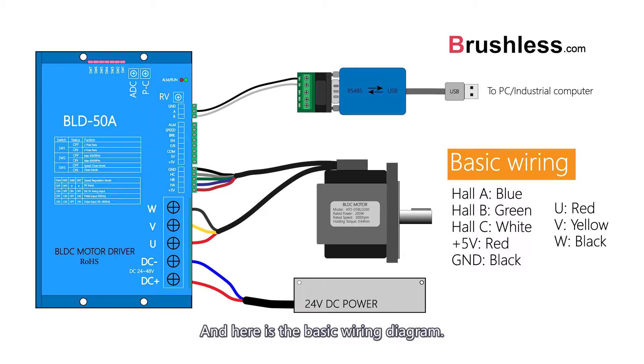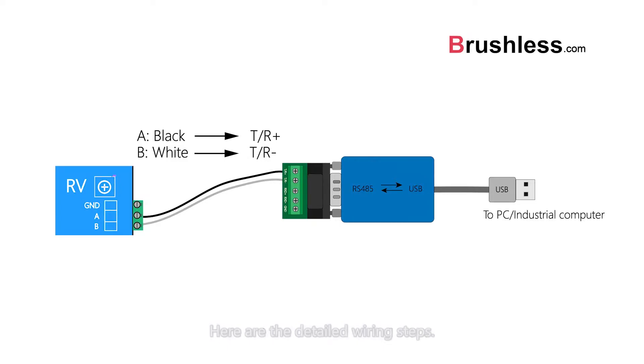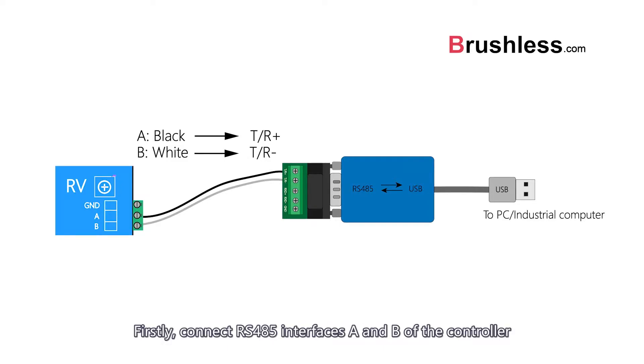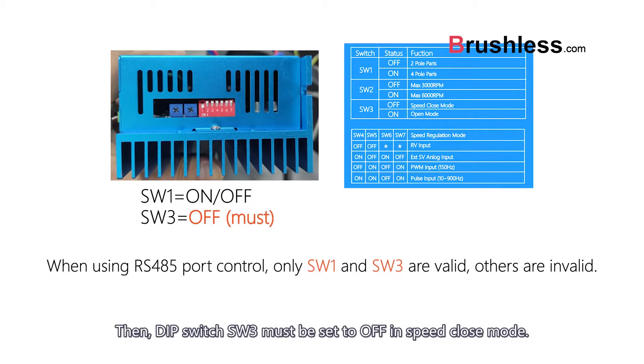Here is the basic wiring diagram and detailed wiring steps. Firstly, connect the RS485 interfaces A and B of the controller to T/R+ and T/R- of the conversion module respectively. Then, DIP switch SW3 must be set to off in speed close mode.